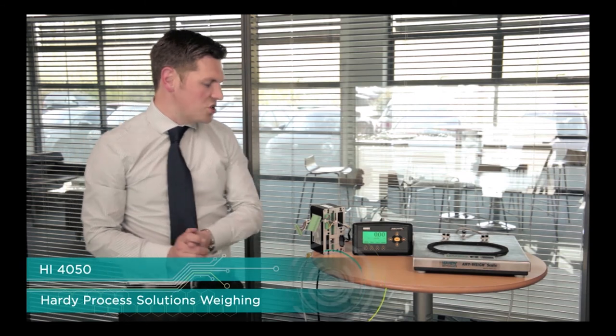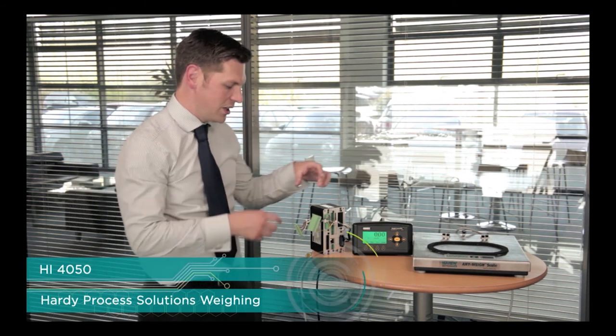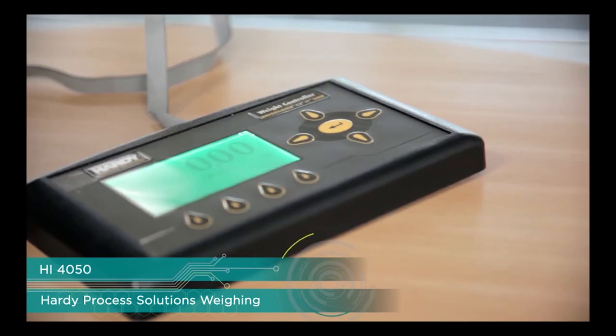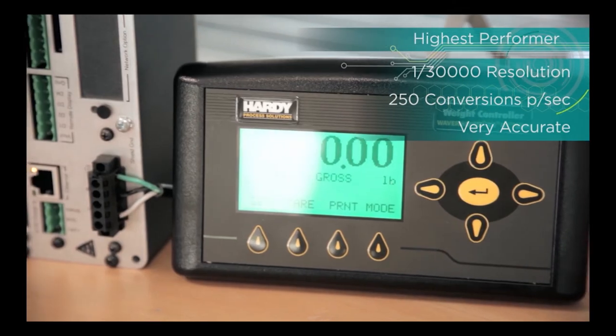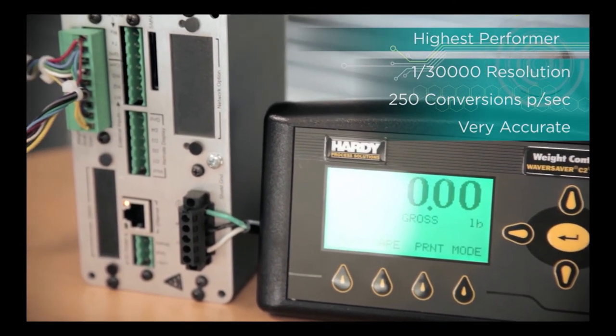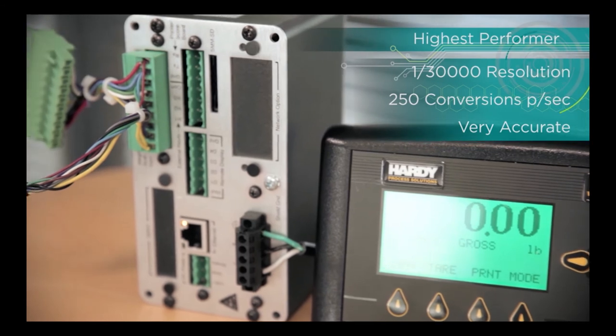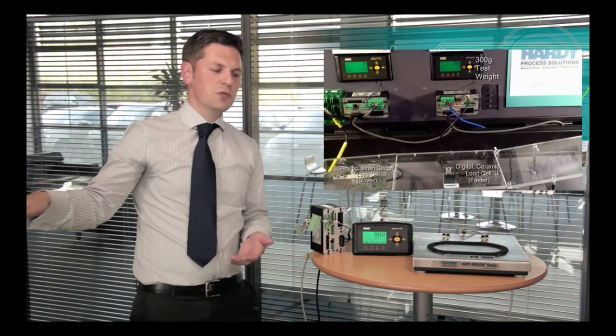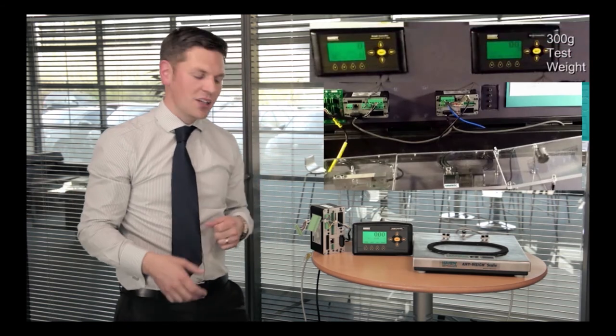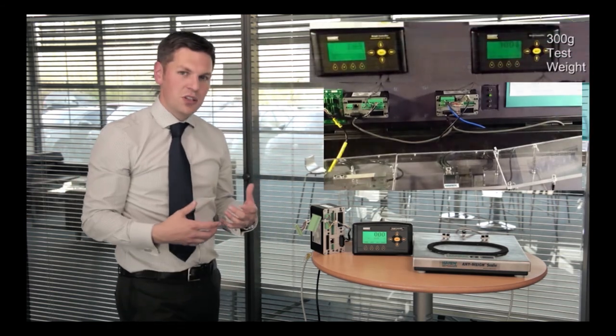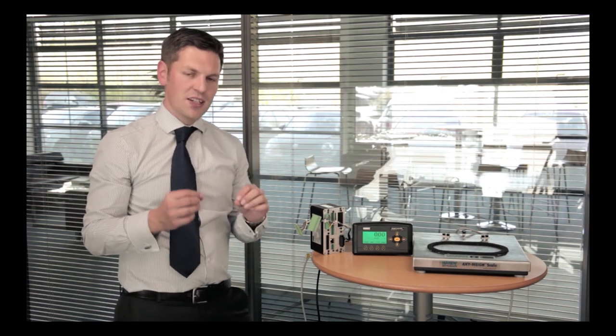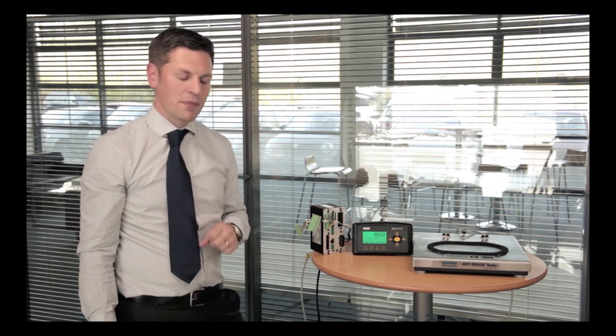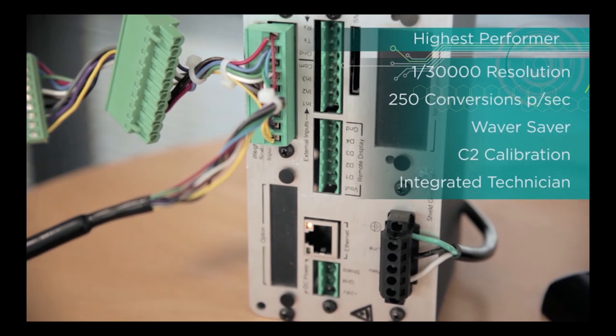This instrument here is the HI4050. It's available in this form factor with an optional screen and is the highest performance that Hardy have got. It does 1 in 30,000 resolution and up to 250 conversions a second. That's really good if you've got a dynamic weigh application, like a weight moving across a conveyor, that kind of thing. It's also good if you need lots of accuracy. With the right sensors, we can really get some precision accuracy with this one.